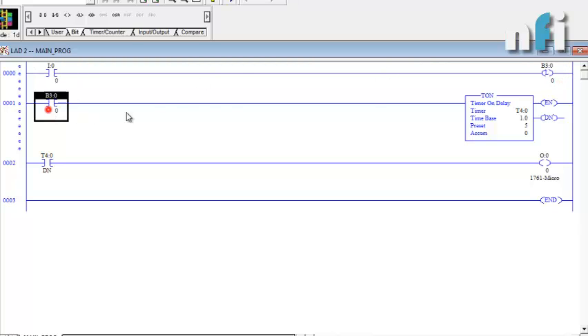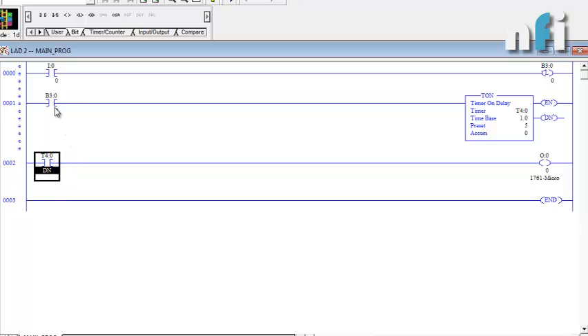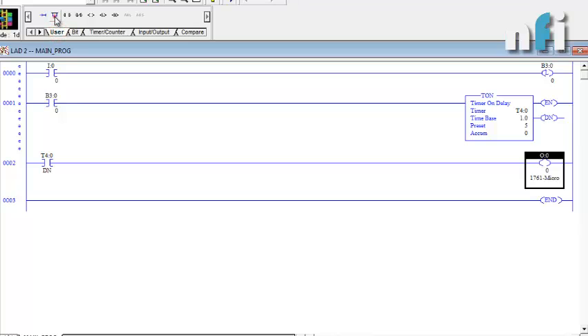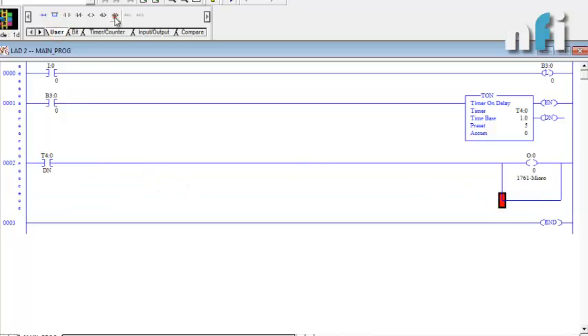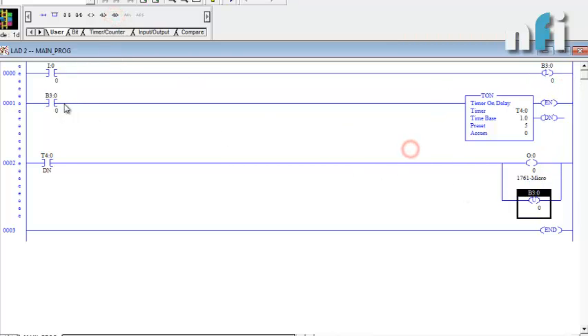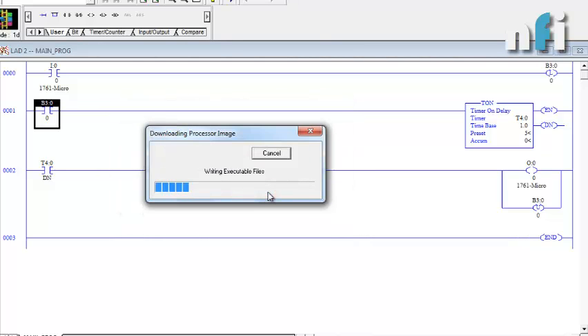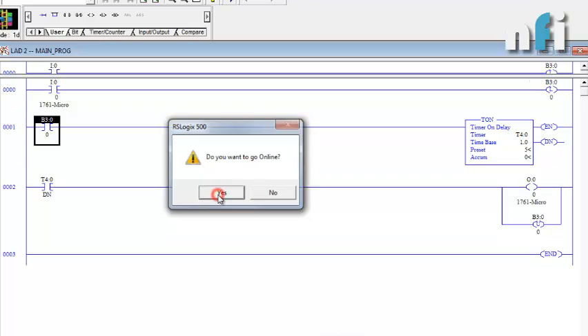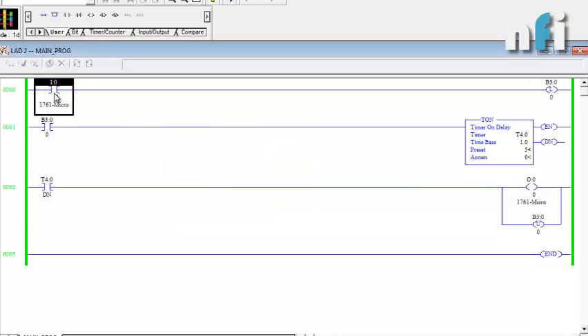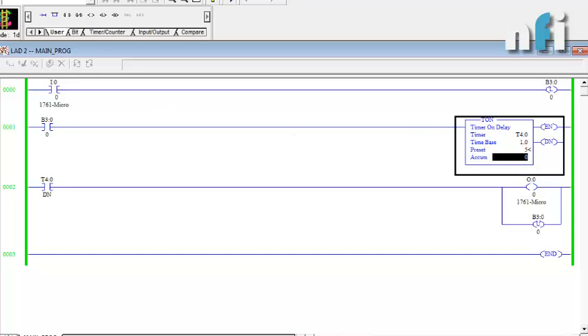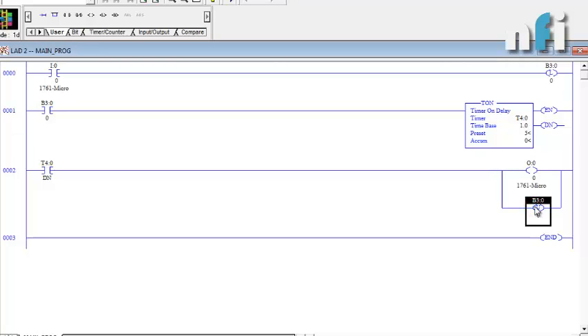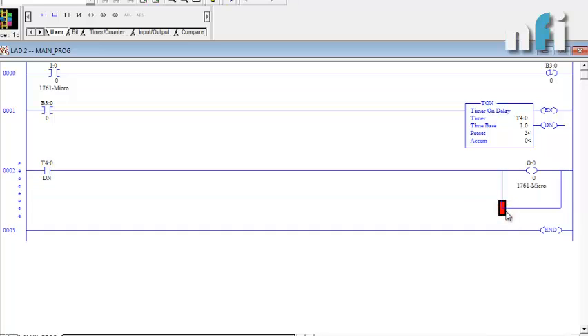I'll take the latched bit as a NO contact to drive the timer. If I press I0 once, it gets latched and turns on the timer — it won't turn off even if I0 is released, because it's latched. When the done bit completes, I'll also unlatch B3:0/0 in parallel with the output so we can restart the operation. The program now means: just pressing the input once, the output will be on after five seconds.